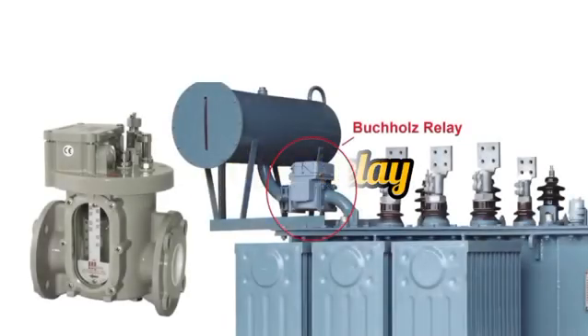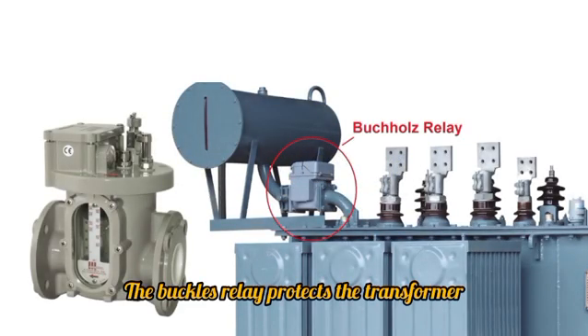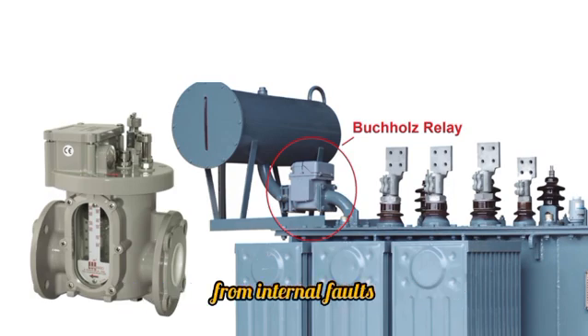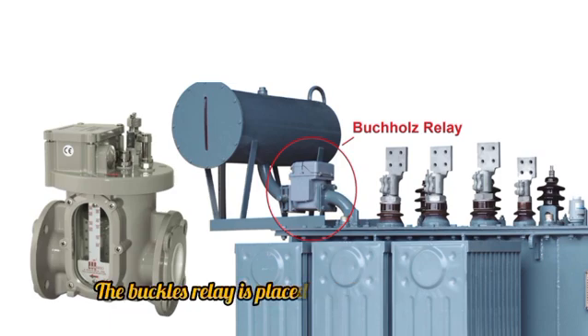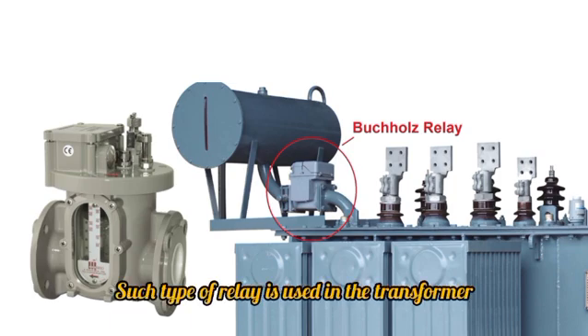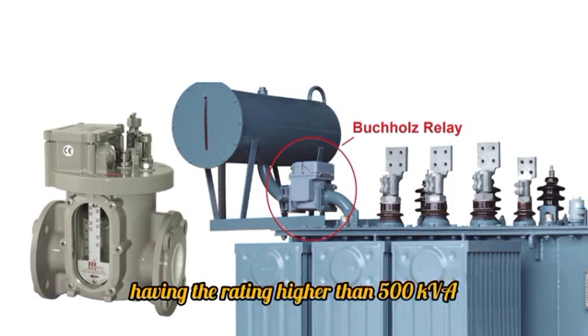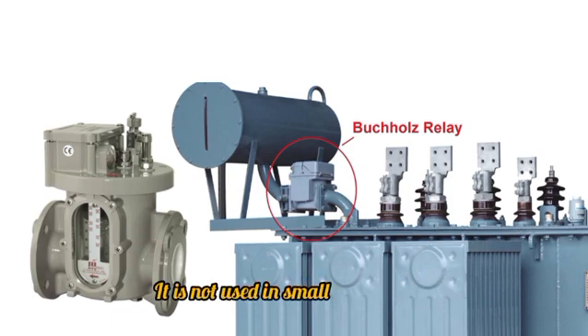Buchholz Relay. Definition. The Buchholz relay protects the transformer from internal faults. It is the gas-actuated relay. The Buchholz relay is placed between the main tank and the conservator. Such type of relay is used in transformers having a rating higher than 500 kVA. It is not used in small transformers because of economic considerations.